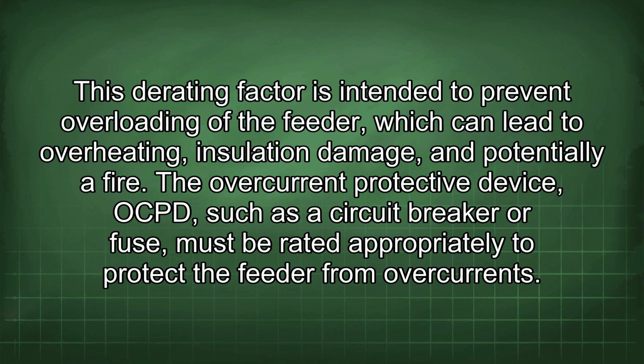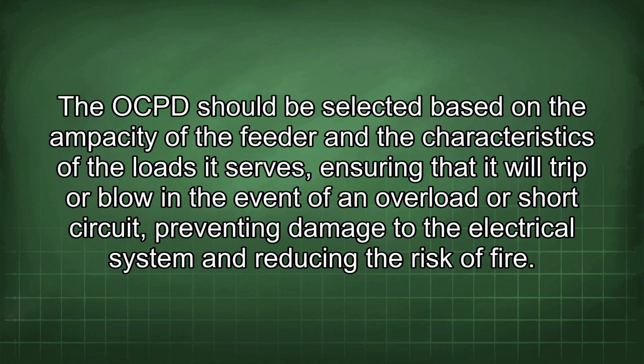potentially a fire. The overcurrent protective device, OCPD, such as a circuit breaker or fuse, must be rated appropriately to protect the feeder from overcurrents. The OCPD should be selected based on the ampacity of the feeder and the characteristics of the loads it serves, ensuring that it will trip or blow in the event of an overload or short circuit, preventing damage to the electrical system and reducing the risk of fire.